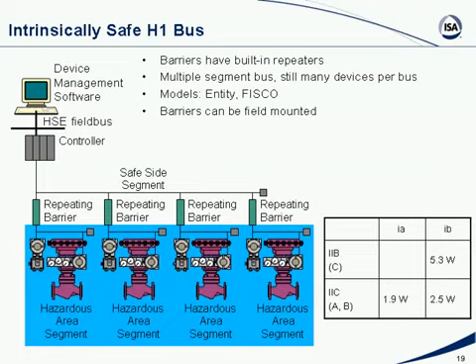These barriers—there are ones in the market that can also be field mounted, which we'll see in the next slide. You should keep in mind you need to use special fieldbus barriers; you can't just use any fieldbus barrier. The number of devices that can connect to one barrier depends on how much power the barrier makes available, which in turn depends on the design of the barrier, which gas group it was designed for, and also the power consumption of the devices.